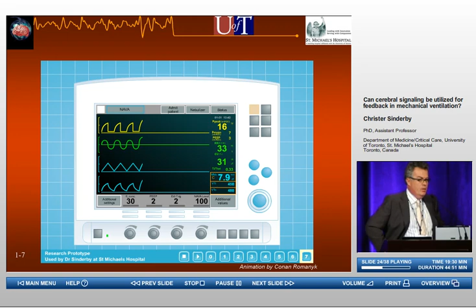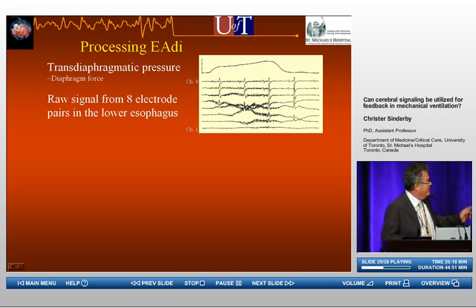I'm not going to go deeply into the processing part because that will take the rest of the day, but the general concept is that we take out a signal, and you see those 8 channels of black cluster at the top there. That's diaphragm activity as it comes out from the electrode. On top of it, you see the transdiaphragmatic pressure. That's the pressure that is generated when a person is breathing, in this case, from functional residual capacity to maximal inspiration. And you could probably tell that there is a little bit more activity towards the end of the inspiration, but it's not so easy to see.